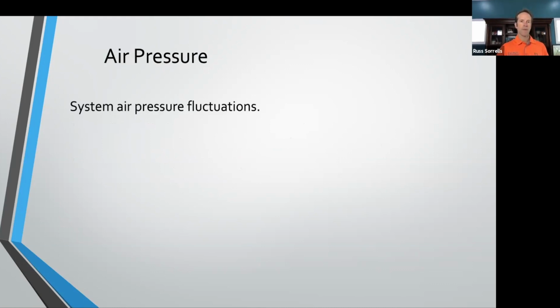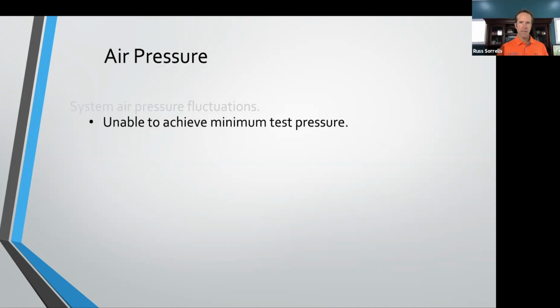So we're going to talk about air pressure settings. If you are unable to achieve minimum pressure, so in the instrument, there are minimum and maximum settings, and the minimum test pressure is the pressure that you must achieve during the pre-fill in order for the instrument to continue to run the test. It's a safety to prevent us from going through the entire cycle of the leak test only to find out that it didn't reach test pressure because it had such a gross leak. We used to call it a gross leak test, but now during pre-fill, if we don't reach that minimum test pressure, it'll kick out. Well, this is a setting inside the instrument.